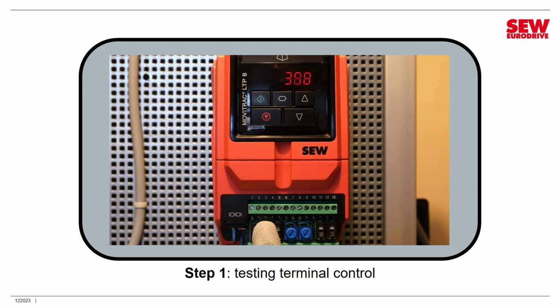We'll go back now. So that works. Now we're going to try the presets. Digital input 3 controls them. It's off right now, which selects the field bus, but when I turn it on, it will switch to presets. Digital input 5 selects between them. We've selected the first one.